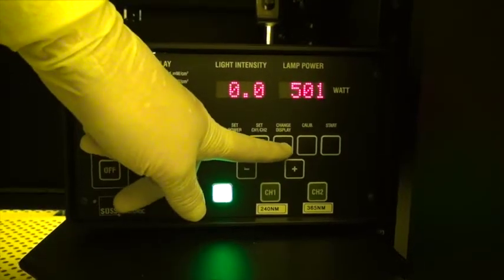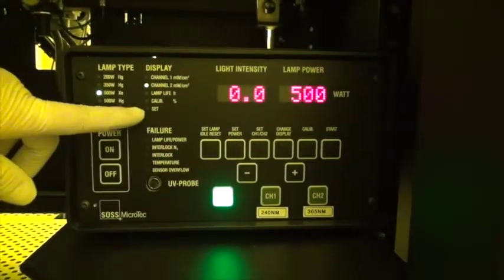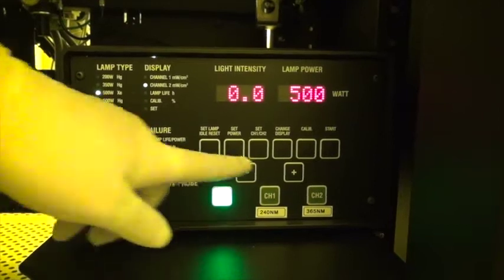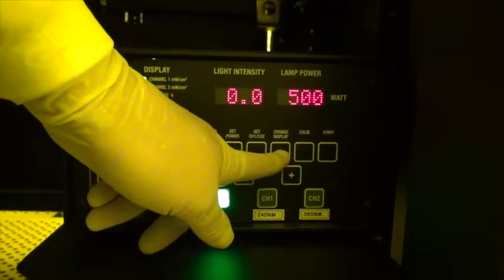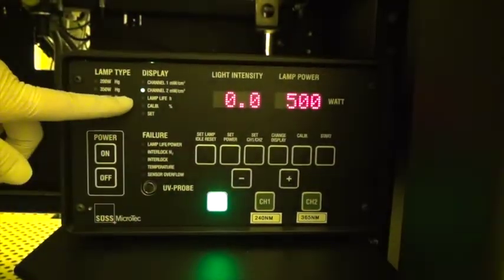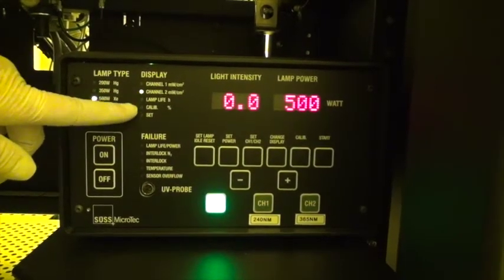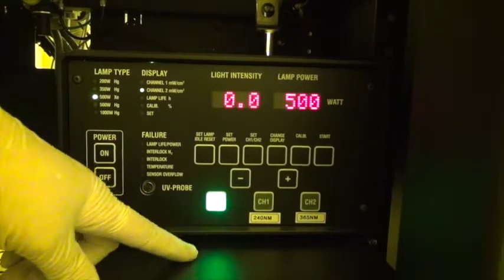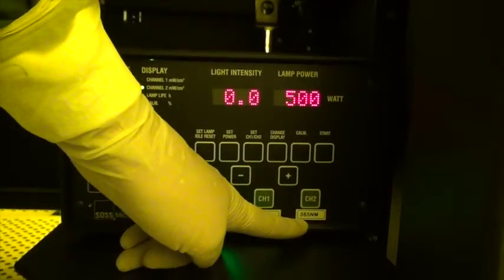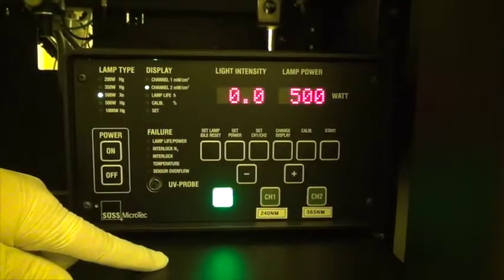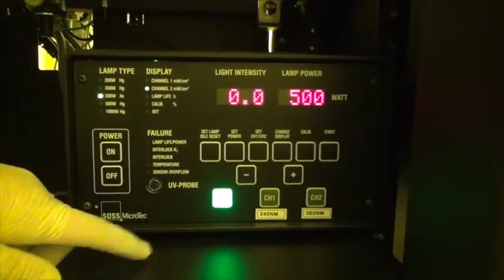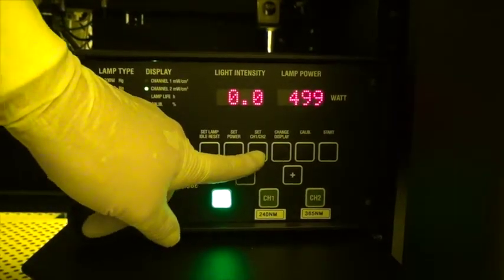Then we use the change display button to make sure that we have selected channel 2. So if I press change display we can cycle through to channel 2. Because channel 2 is the one we want to use. That is the intensity measured at 365 nanometers as indicated here. So once we have channel 2 selected we can press set CH1 CH2.